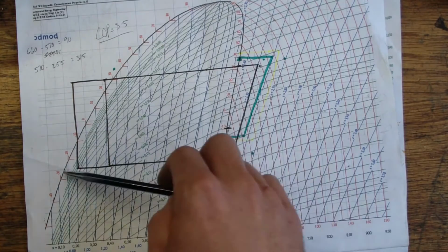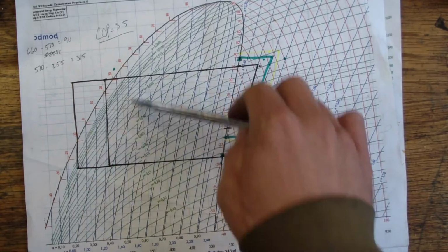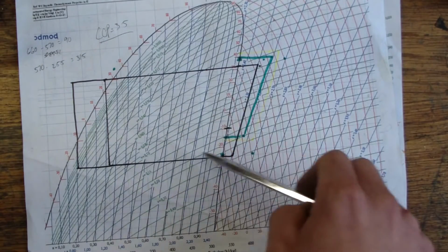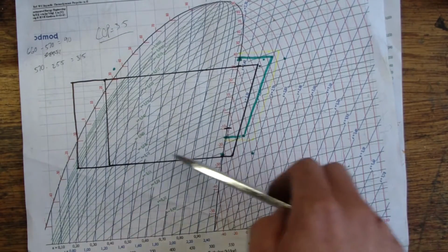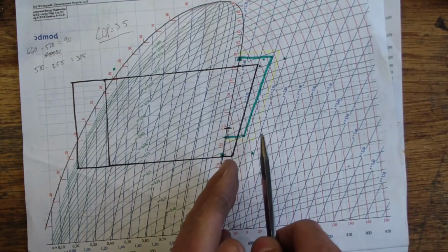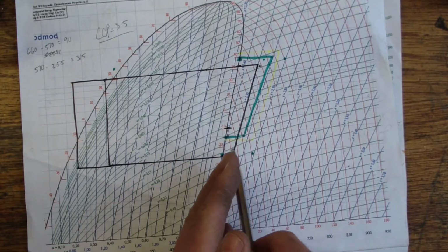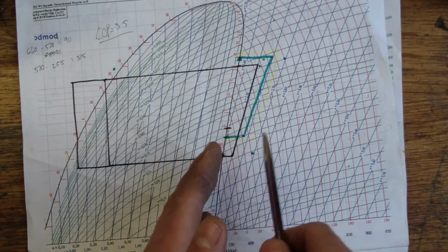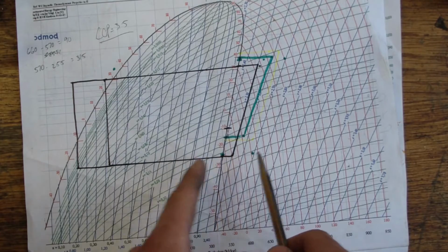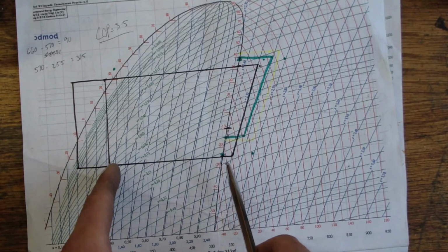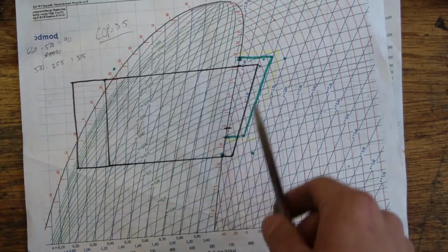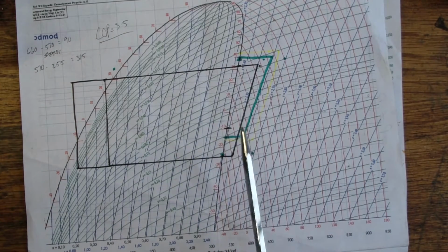So a lot more of the refrigerant had to flash off to cool the refrigerant that we couldn't cool in the condenser. So there's less liquid being circulated that's actually doing cooling work. So not only did the magnitude of the enthalpy change during compression increase, but the magnitude of the enthalpy change for evaporation decreased. So we can see how our overall COP decreased.